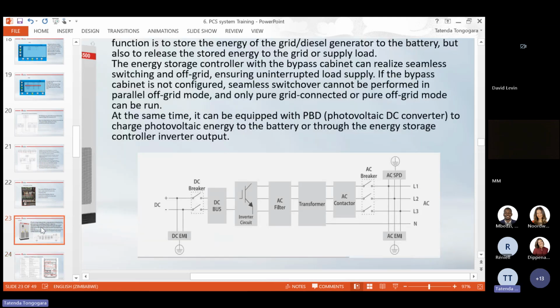Just a quick note on when you're designing your PCS system: look at the amount of inductive loads on site. If you have motors that are 10 kilowatts and above, it's best you put them on drives. And then your inductive loads should not exceed 50% of your PCS when they are on drives.